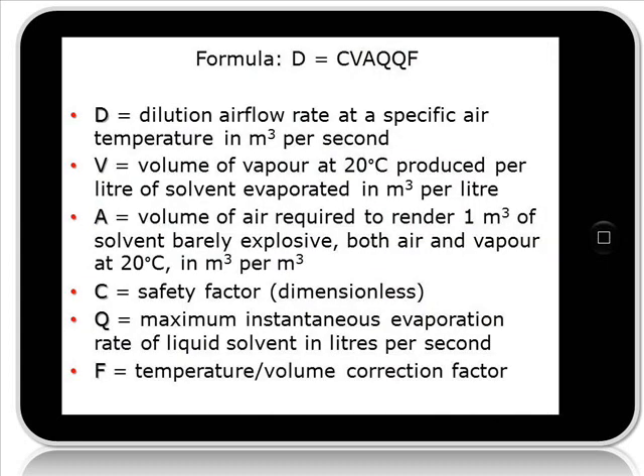D is the airflow rate at a specific air temperature in cubic metres per second — that is what we will be calculating. V is the volume of vapour at 20 degrees C produced per litre of solvent in cubic metres per litre. A is the volume of air required to render one cubic metre of solvent barely explosive, with both air and vapour at 20 degrees C, in units of cubic metres per cubic metre.